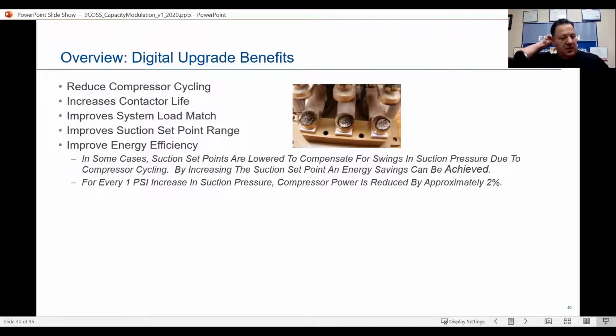Here's something we talk about a lot in our classes. In some systems, suction set points are lowered to compensate for swings in suction pressure due to compressor cycling. By increasing the suction set point, energy savings can be achieved. I think we all know that, but did you know for every 1 psi increase in suction pressure, compressor power is reduced by approximately 2%? Now, when they say power, we're not talking about the capacity. We're talking about the energy savings, okay? The electricity. We're reducing that electric bill by approximately 2%, okay? So that's huge. So remember that suction pressure, how important that is, keeping that suction pressure up.